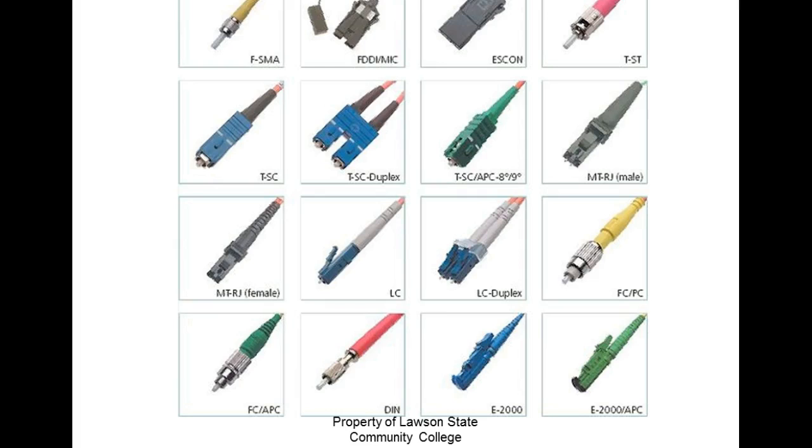What else do I have? I don't see anything else, guys. I think I brought out all the cables I have back over here. So the FC/PC cable is used predominantly for single mode fiber, and in multi-mode fiber, the ST and the SC are the most popular.